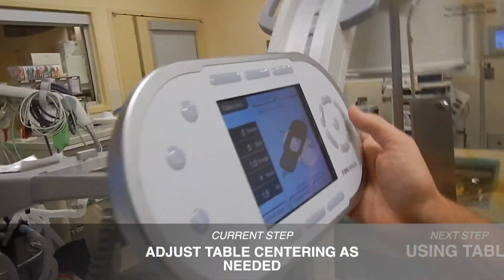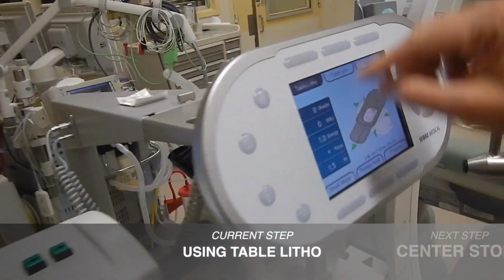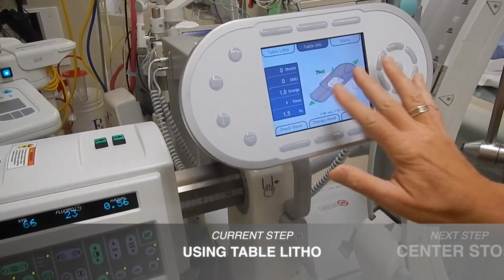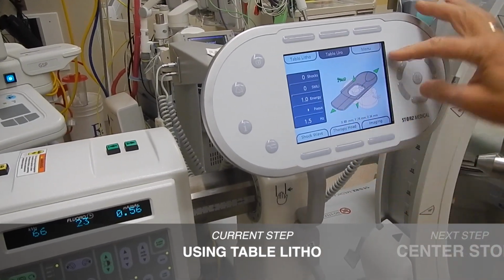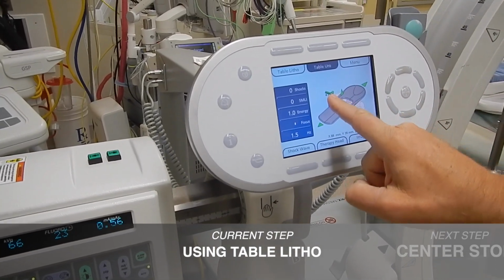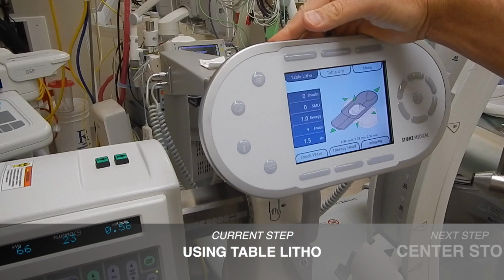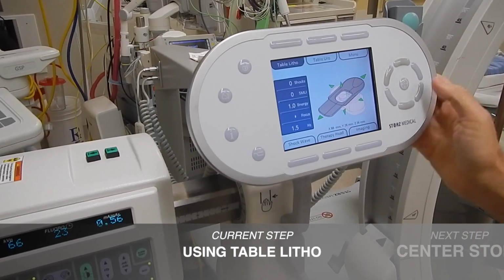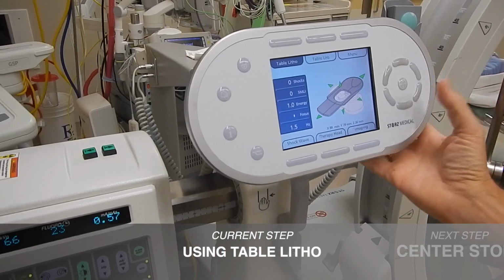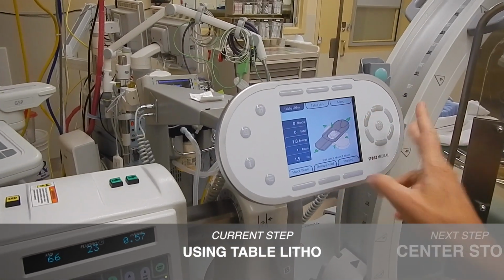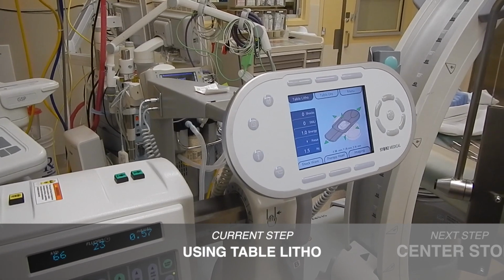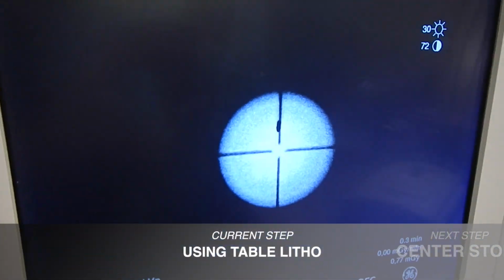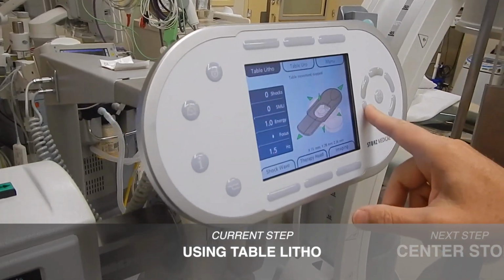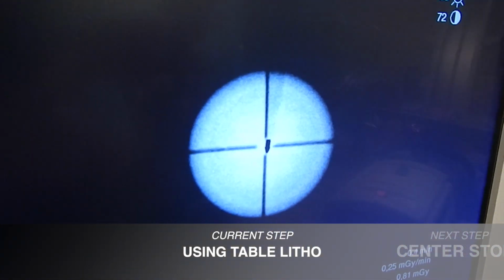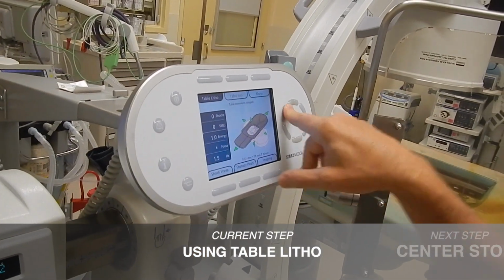So what you're going to do is move the table controls. Are you in litho or uro? Table litho. Okay. If you're in table uro, all the controls are the same except these ones, the side to side. That becomes Trendelenburg now. So you don't want to be in that. You want to be in table litho, so you see all these arrows. I moved it laterally, so it's going more towards the center. It's still too high, so now I'm going to move the table down. Obviously the patient can't help now because they're asleep. And then you just fine tune it into the center of the crosshairs.